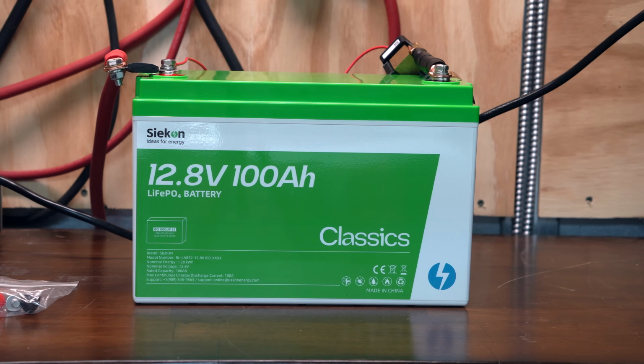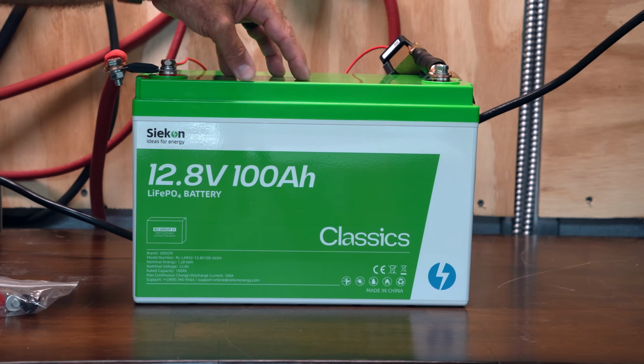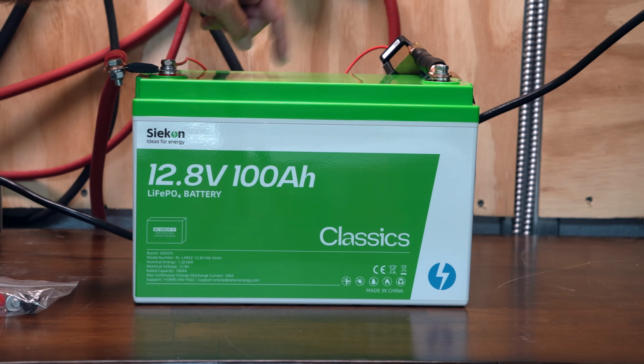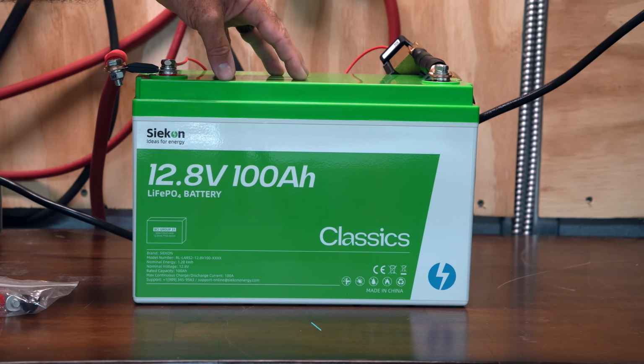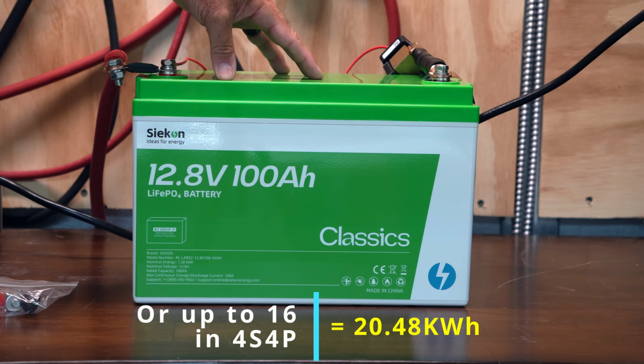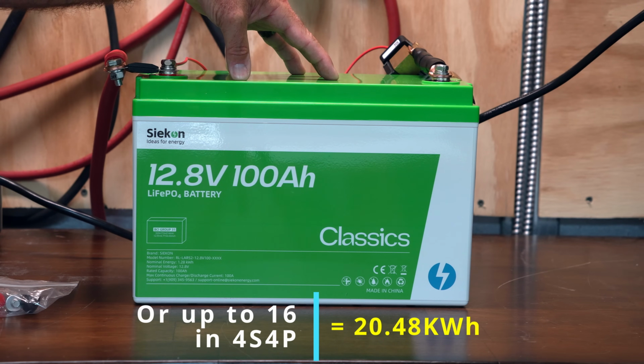Group 31, as I mentioned, is the proper designation for this particular format. You can put a maximum of 4 of these in parallel or 4 in series with that 100 amp BMS that it has. That means you can actually do a 4S4P configuration, which would be 16 batteries total, and that would give you, I think, a little bit over 20 kilowatt hours of battery capacity.